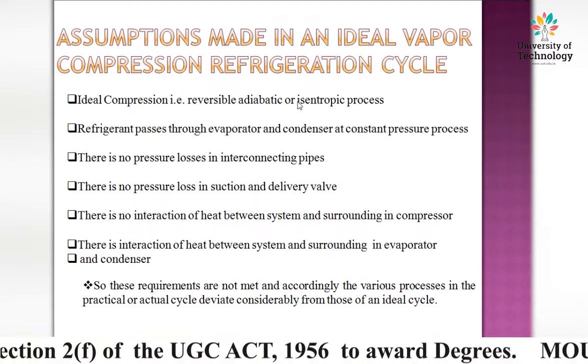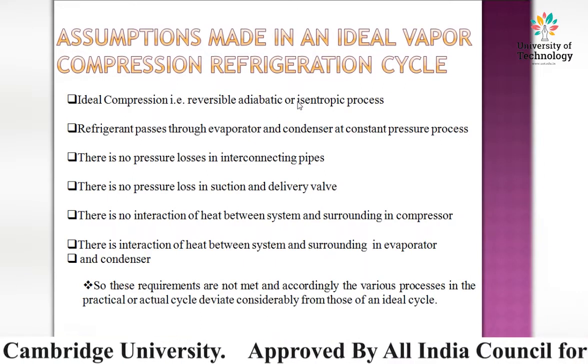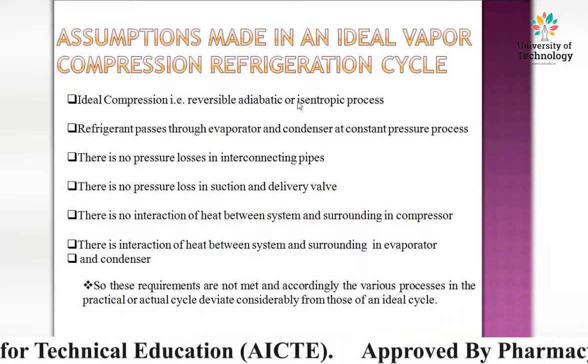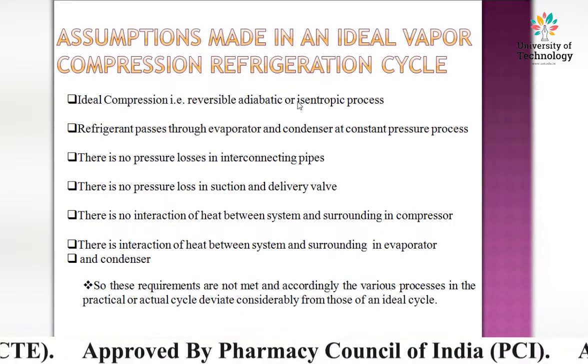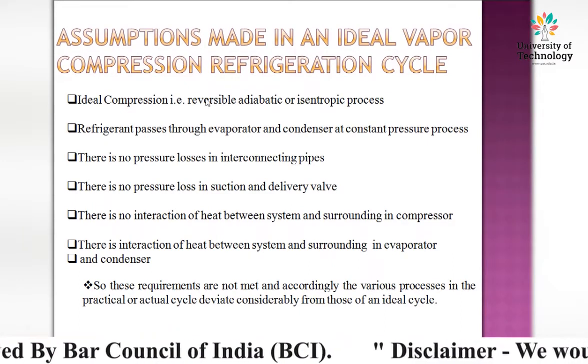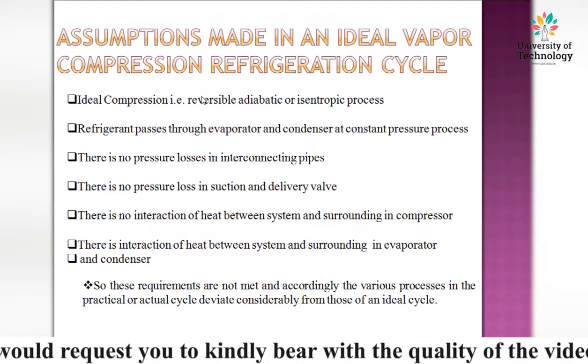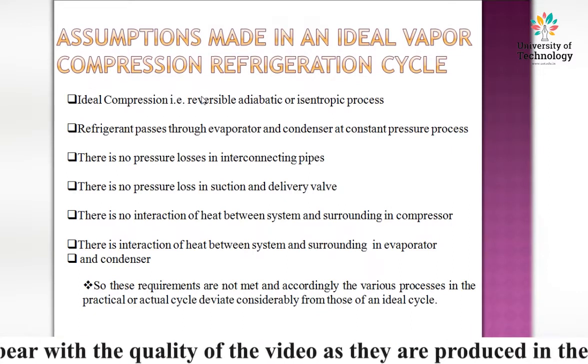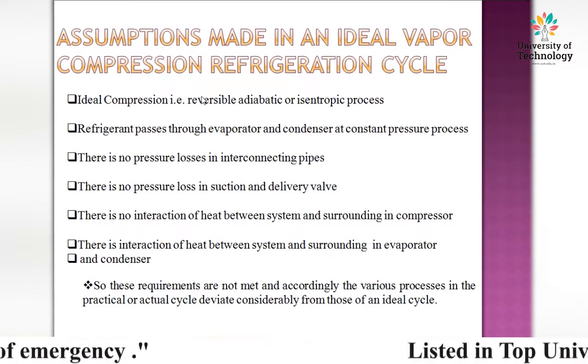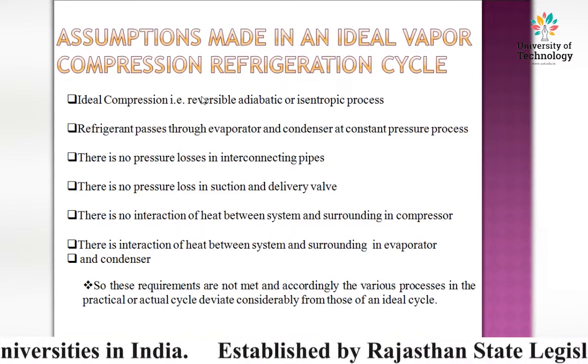In the ideal compression cycle, the refrigerant passes through the evaporator and condenser at constant pressure. There are no pressure losses in any interconnecting pipes or in the suction and delivery valves. There is no heat interaction between the system and surroundings during compression — no loss of heat takes place in the compression process.